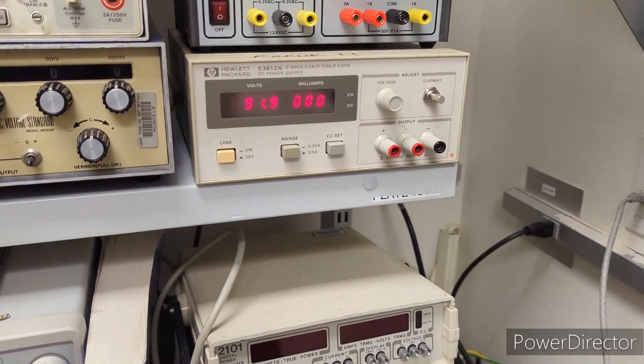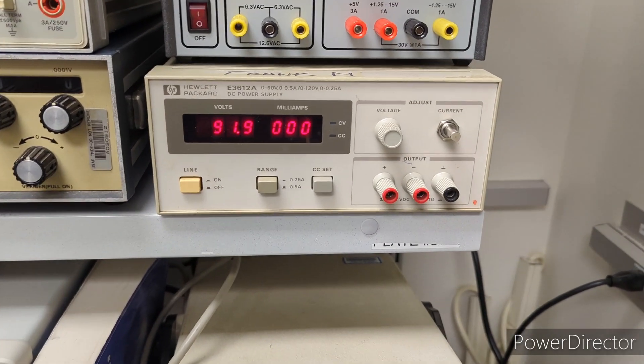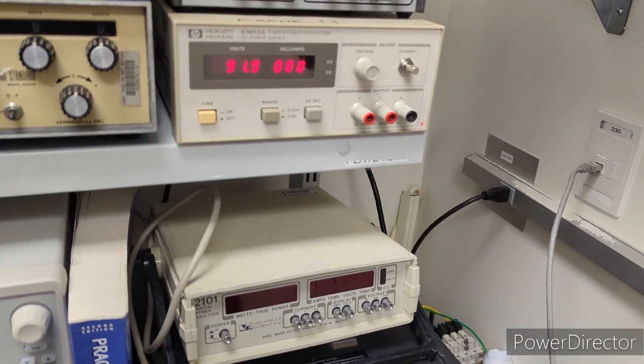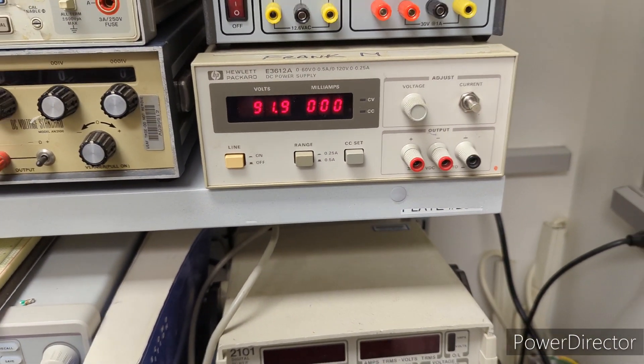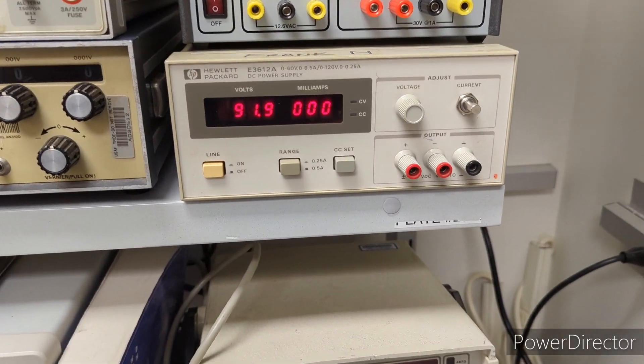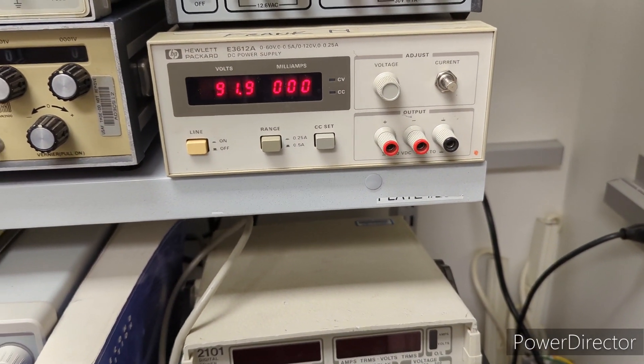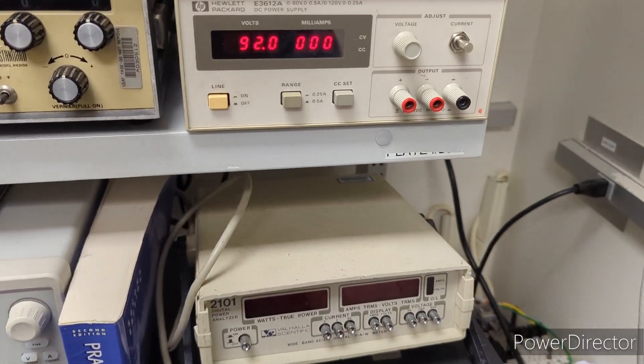I have another repair video for this HP E3612A DC power supply. It has a max voltage of 120 volts at 0.25 amps and can also do 60 volts at up to 0.5 amps. It had a unique symptom: regardless of what you set the current control to, it would only limit to 60 milliamps. You could set it to 0.5 amps, put a load on it, and it would only limit to 60 milliamps.